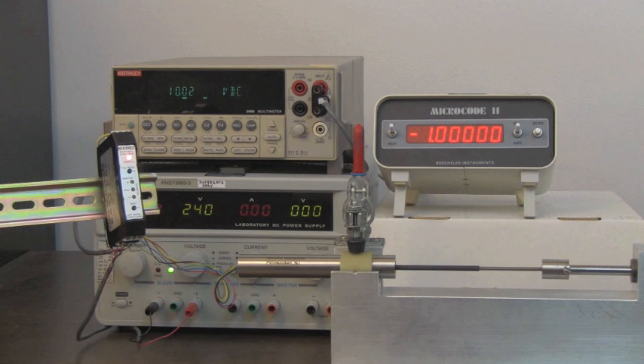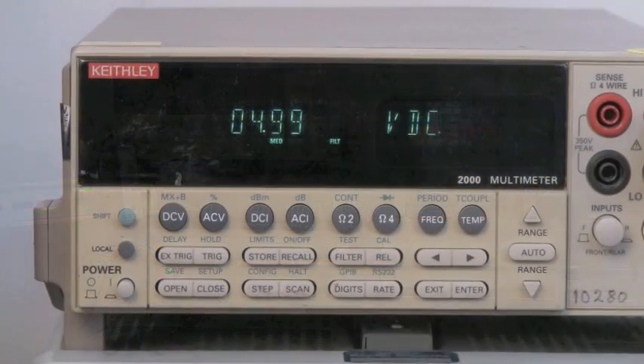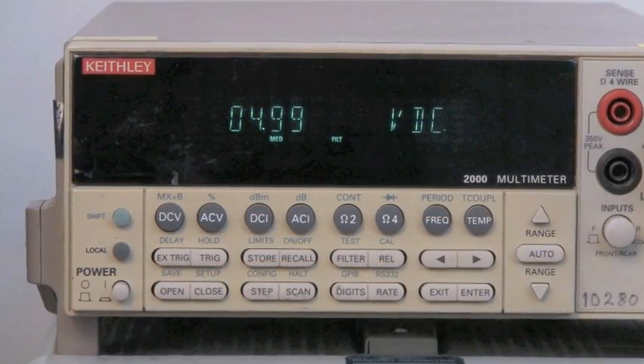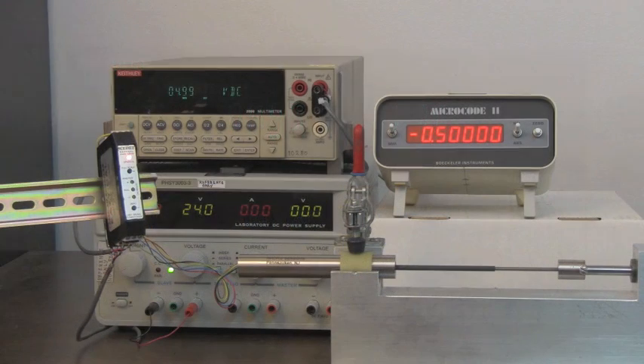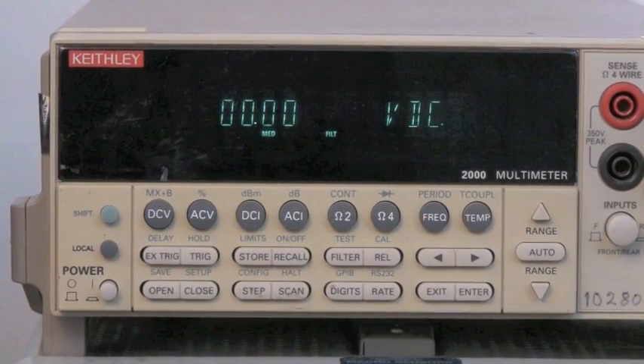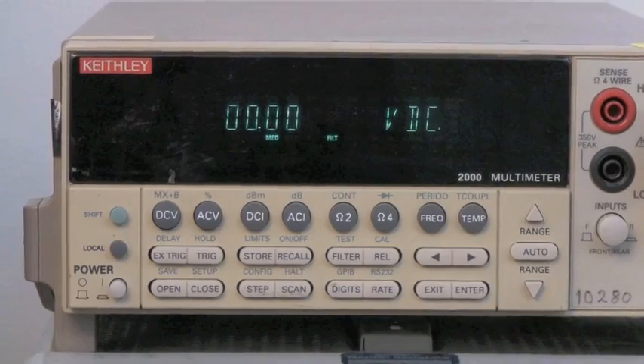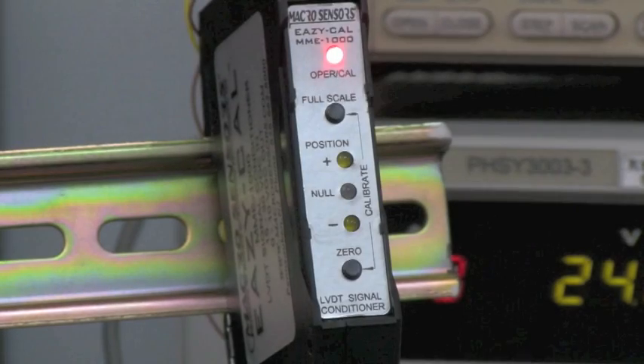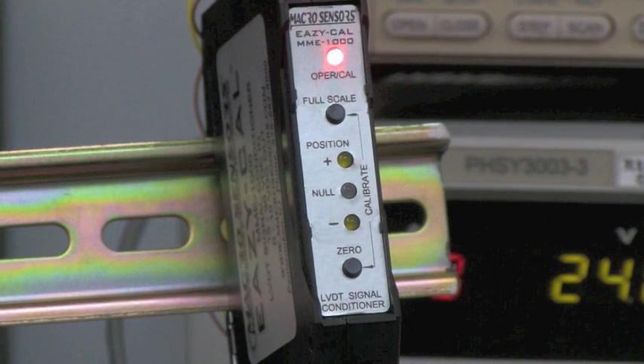We now displace the LVDT back to the plus 0.5 inch position and we observe the output to be plus 4.99 volts DC with plus 5.00 volts DC being nominal. Finally, we displace the LVDT back to the 0 inch position and we observe the output to be 0.00 volts DC. Calibration has now been successfully completed and the EAZY-CAL is ready for normal operation.